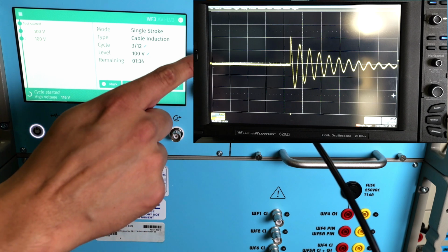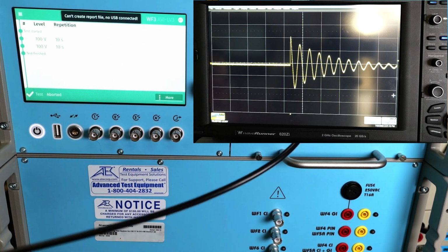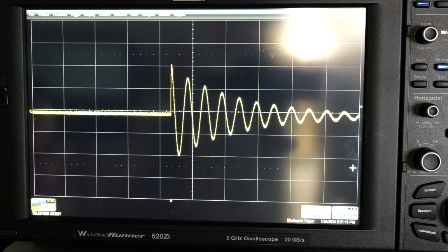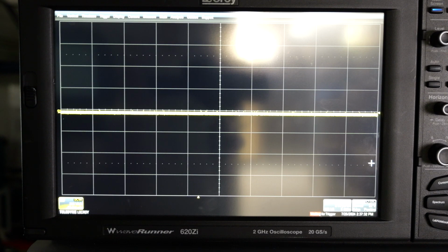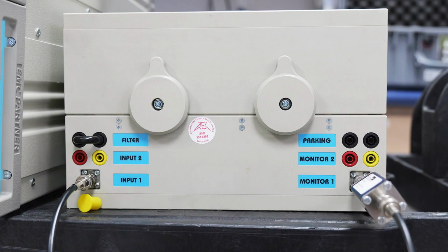And I have my differential probe connected to the monitor 2 port on my BT7 current injection probe. But just keep in mind you want to follow these test diagrams so you know where to hook everything up. So now let's go towards the short circuit part of this test by now using the shunt adapter on the monitor 1 port. For this next test, we're going to do the short circuit waveform 3, and we're using the shunt, which is connected to the monitor 1 port on our BT7 current injection probe, and I have that connected to our oscilloscope channel 1.